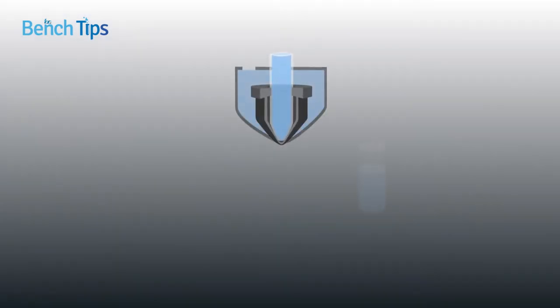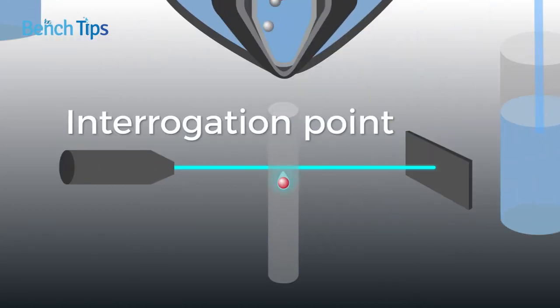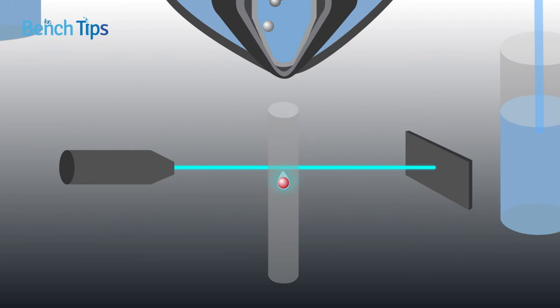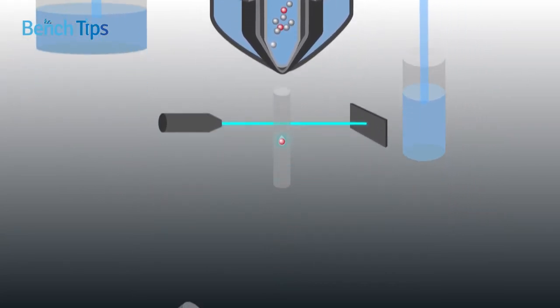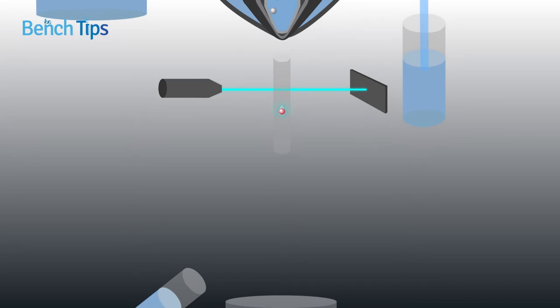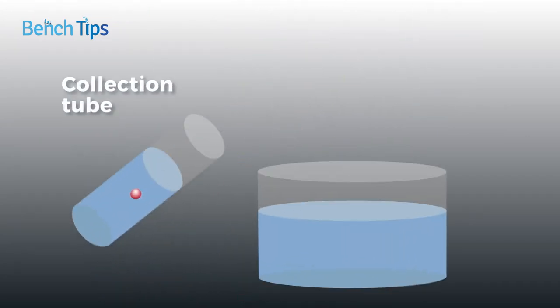As the cells enter the sorter, they are injected into a stream of sheath fluid that is forced through the system under high pressure. They then move past an interrogation point and the stream is partitioned into droplets each containing a single cell. By applying a charge to the droplets containing the cell type of interest, the cell sorter directs the target cells into a collection tube as they pass through an electric field, allowing them to be used for further analysis.